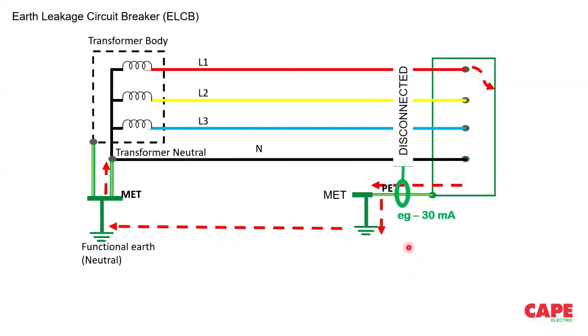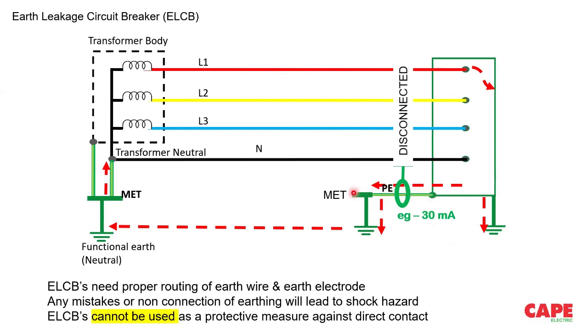ELCBs are very critical while doing earthing. For example, in your installation or in your equipment, if you have one more earth leakage path, then you cannot achieve safety in this particular case, because the ELCB is measuring current only through one wire, but you have 2 wires which are connected. As a result, ELCB will not be efficient. It is very important to understand that this particular route where I am showing the cursor, the earth return path, as well as the earth electrode, both must be 100% proper. If there is a loose contact in this wire, or if there is no earth electrode, under these conditions, ELCB will not work properly. So both the route of the earth leakage path and the earth electrode are important for an ELCB to work.